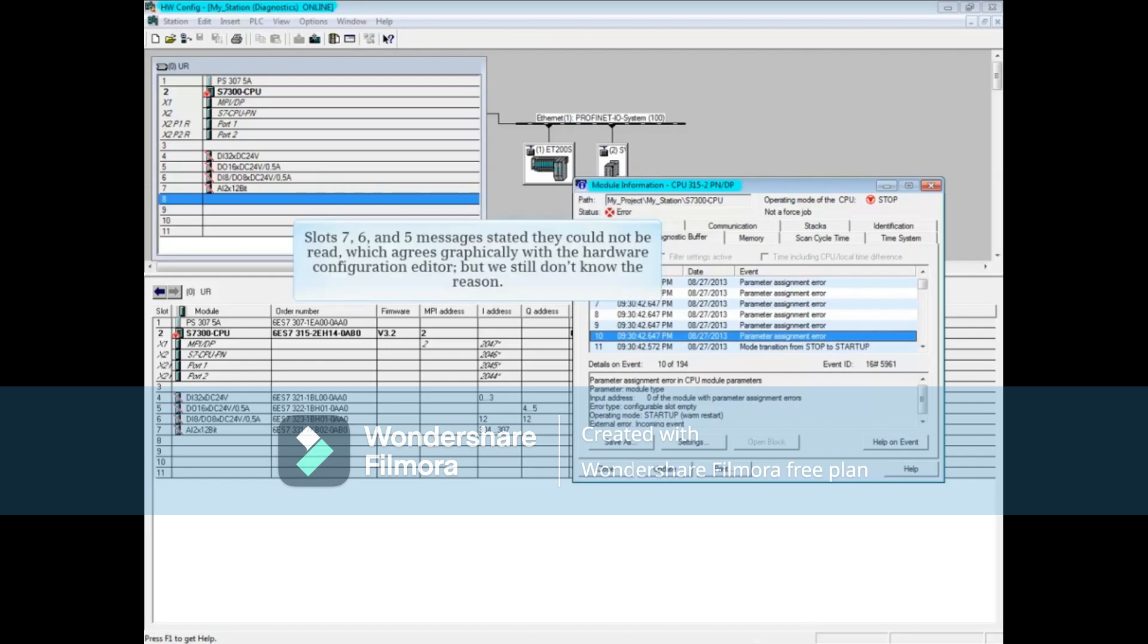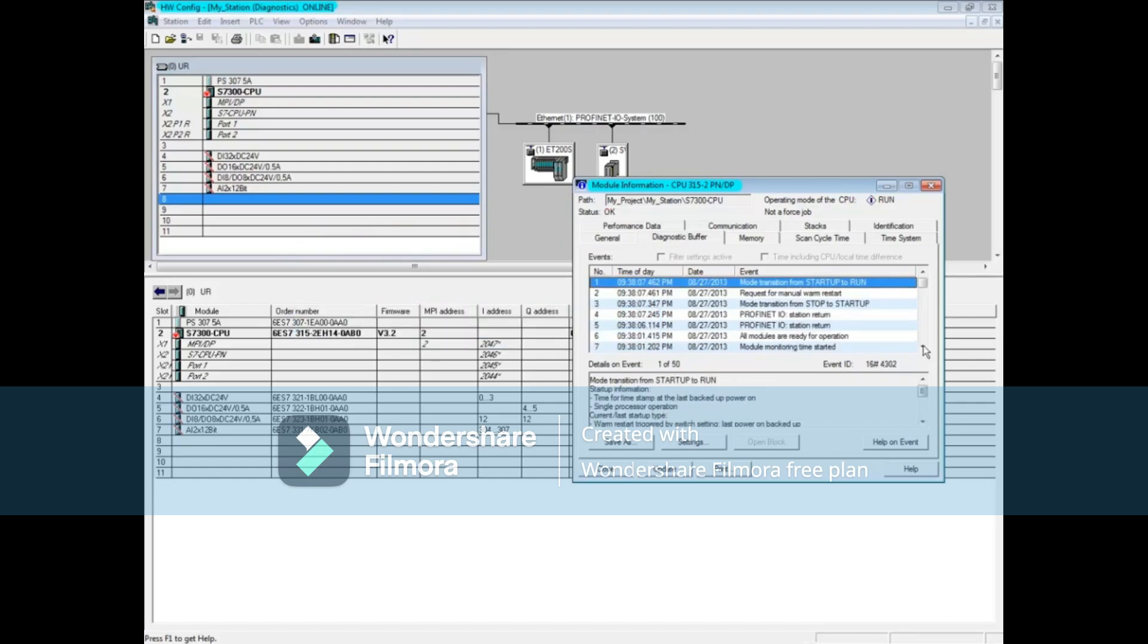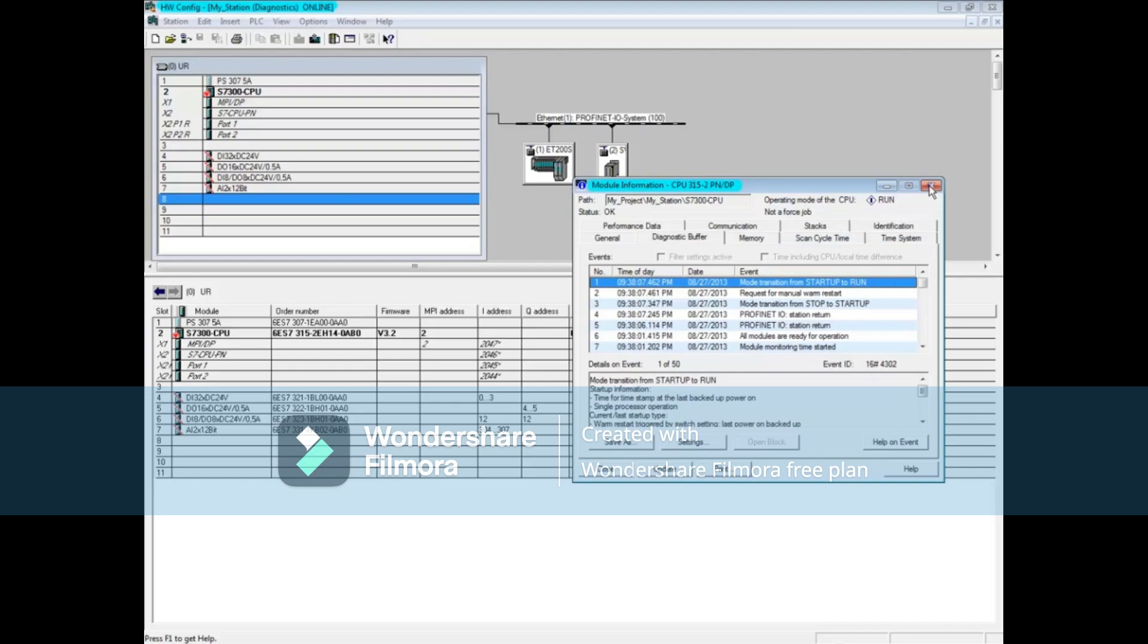We had a message saying slots 7, 6, and 5 could not be read. This agrees graphically with what we see in the hardware configuration editor, but we still don't know why. Now we're going to have to do a physical check of the modules in the rack. We'll close the diagnostic buffer and go look at the physical rack to see if we can determine what's happened.